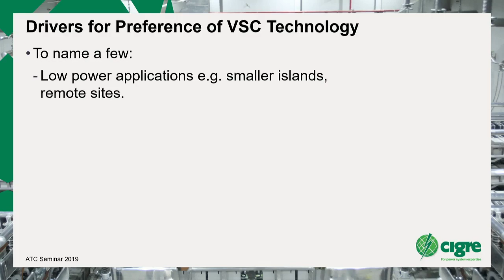They're starting to use it for some offshore loads, and these loads tend to be quite small. So now you have an option if you have an oil platform some distance away from shore. The picture there is Troll A off the coast of Norway, and that's 40 megawatts. Somewhere in the middle of that platform, they've actually built a VSC HVDC converter. So those applications still exist.